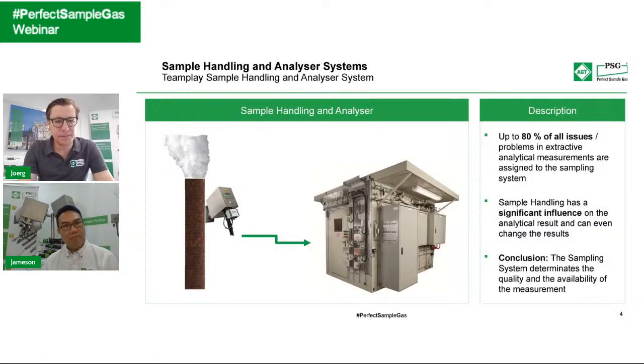The PowerPoint slide I've taken here is one slide from a presentation we had at the CEM conference, a virtual event this time, and it shows the importance that the effect from the sample handling system on the gas probe, or the probe we would like to analyze, has to be reduced to the absolute minimum. And all the effects we are going to see here are the complete opposite. Condensation will cause damage to the probe, or will finally change the probe. And the conclusion of the presentation I gave at that time was really that any changes from the sample handling system have to be avoided.